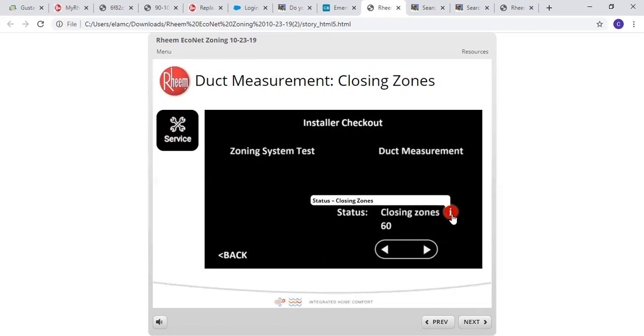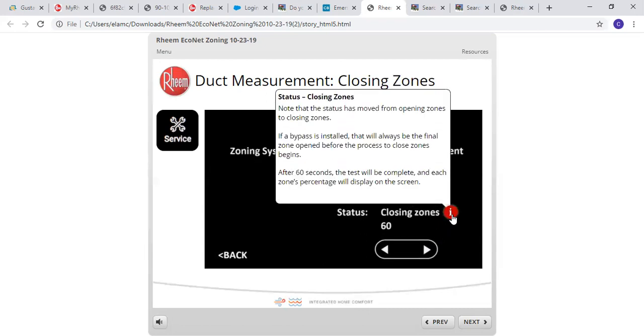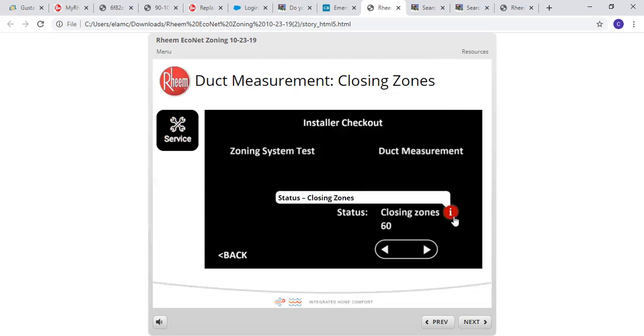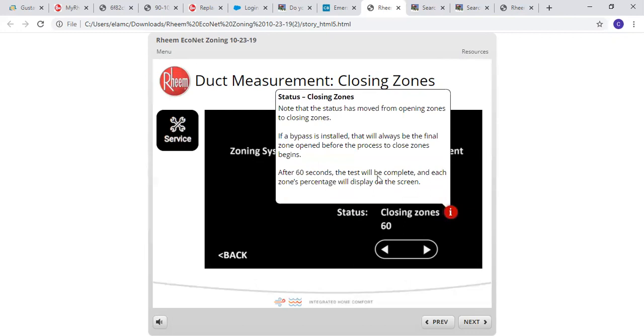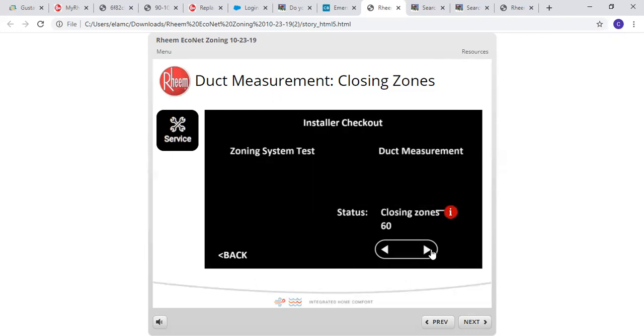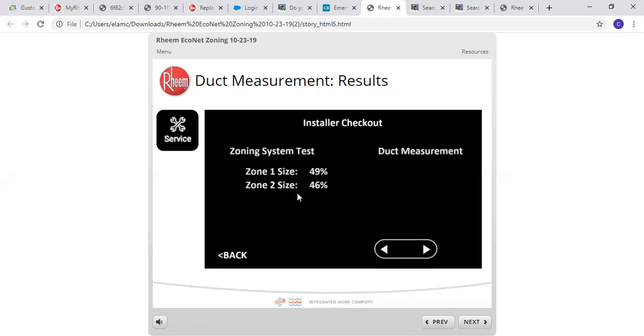Closing zones. Note that the status has moved from opening zones to closing zones. If a bypass is installed, that will always be the final zone opened before the process to close zones begins. After 60 seconds, the test will complete and each zone's percentage will display. In this case here, we're saying zone 1 can handle up to 49%, whereas zone 2 is a little smaller. It can only handle 46%.